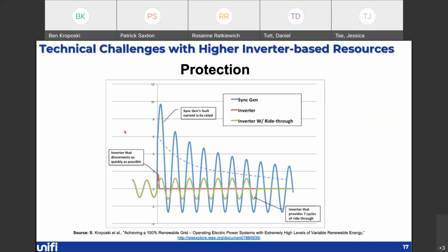But here's the big challenge in a nutshell with inverter-based resources versus synchronous generators. Typically when a fault occurs, say here at time 0, a synchronous generator will put out something around 6 times rated fault current. It's a big spike in fault current. It's easily seen if you are watching the waveform. And so devices can see this and react to it, whether it's a relay, a breaker, a fuse, whatever protection equipment you're using. But for inverter-based resources, they typically don't have the capability to do that high level of output.